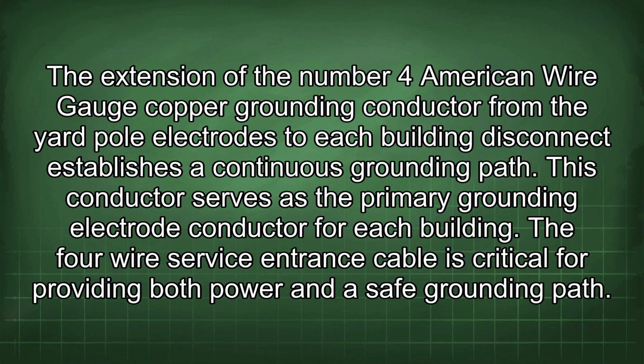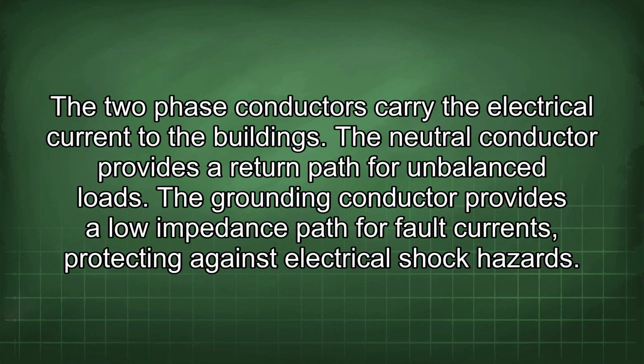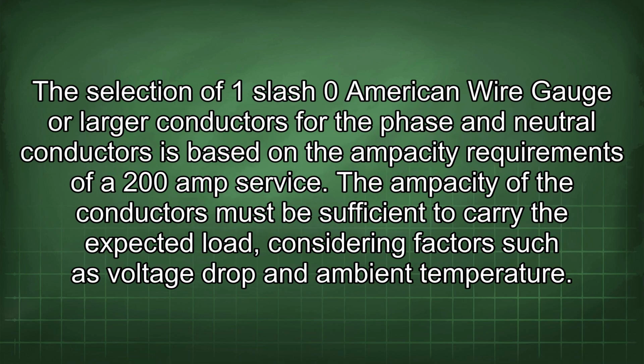The 4-wire service entrance cable is critical for providing both power and a safe grounding path. The 2-phase conductors carry the electrical current to the buildings. A neutral conductor provides a return path for unbalanced loads. The grounding conductor provides a low impedance path for fault currents, protecting against electrical shock hazards. The selection of 1/0 American wire gauge or larger conductors for the phase and neutral conductors is based on the ampacity requirements of a 200 amp service. The ampacity of the conductors must be sufficient to carry the expected load, considering factors such as voltage drop and ambient temperature.